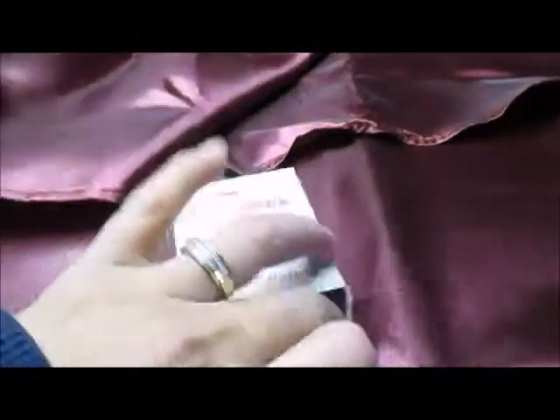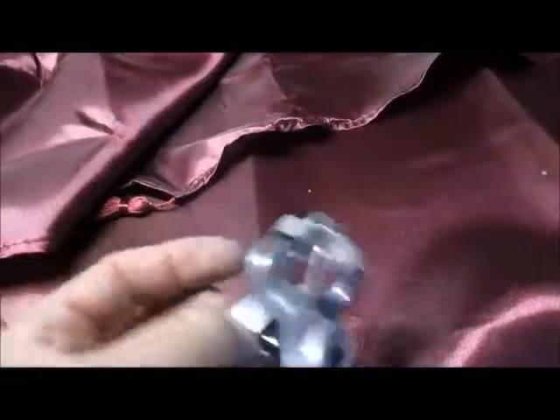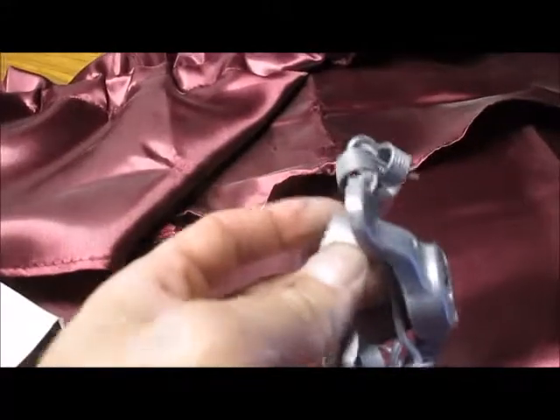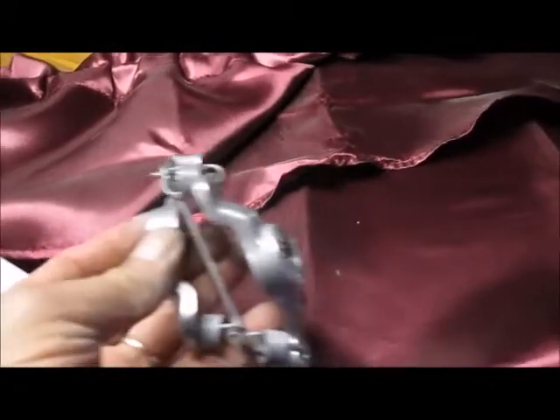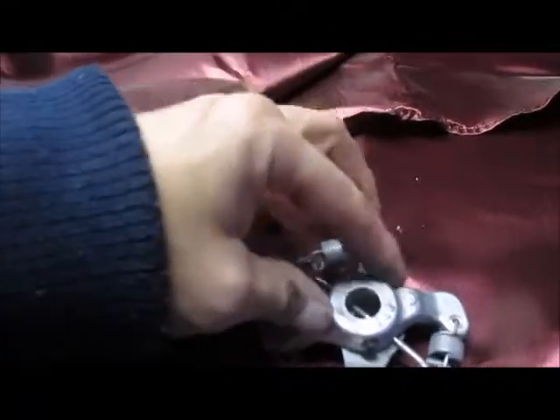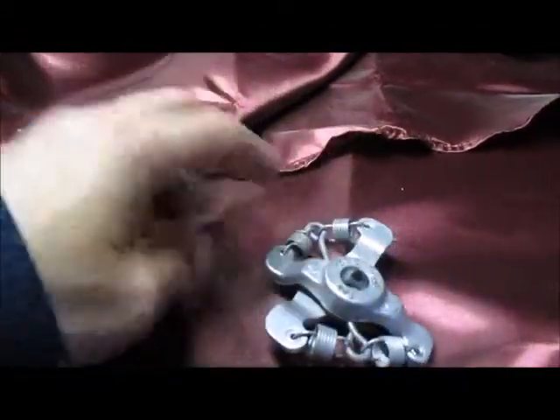Remember I said don't stick your finger between the motor and the impeller? Well, this right here, you see there are little Allen screws on both sides. One gets attached to the actual impeller, and one gets attached to the motor, and they spin. It spins the impeller, the motor though, it's a 1/3 or 1/4 horsepower motor that spins the impeller, but you have to put these on with an Allen wrench, and it was a pretty tight squeeze that I had here.